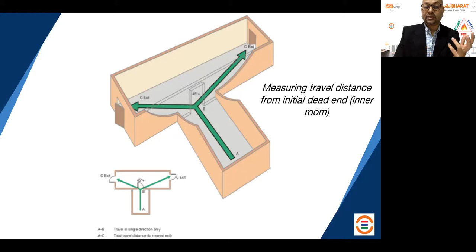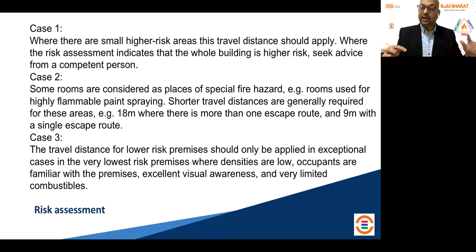So there's a risk assessment you can look at: is the area a small, medium, or high risk? What are the things involved—is there any combustible fire hazard, or none at all? Based on the nature of that assessment, you can decide what travel distance is permissible. The code may allow 45 meters, but if your dead end A to B distance is higher and contributes 70% of your travel distance, it's better to treat that as a dead end corridor and see how it can be mitigated.